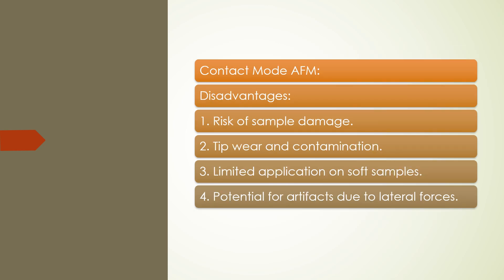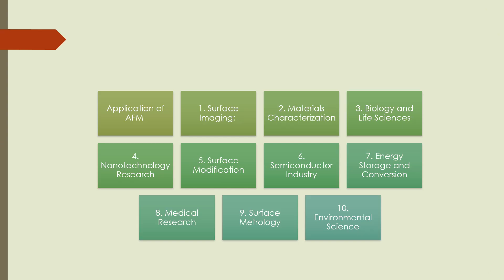Operating in contact mode has disadvantages: the sample can be damaged and the tip needs to be changed frequently due to wear. If the sample is soft, contact mode cannot be used. There is also a risk of getting artifacts on the sample because of lateral forces.